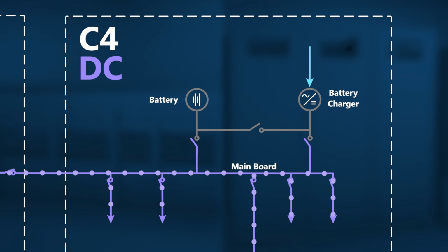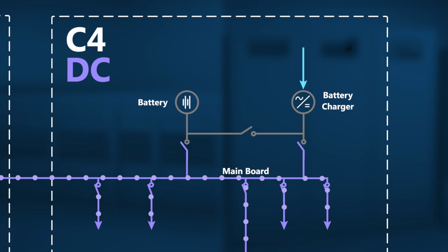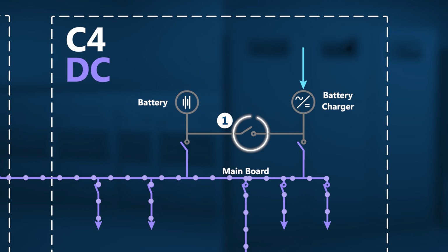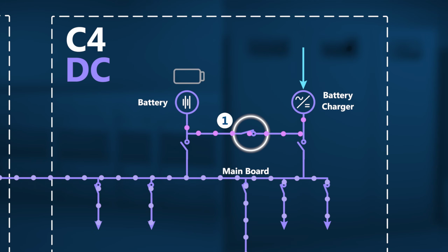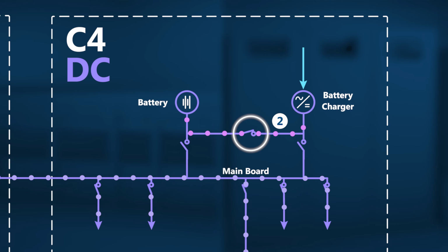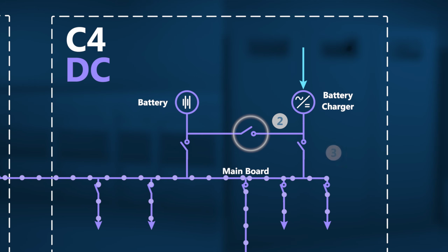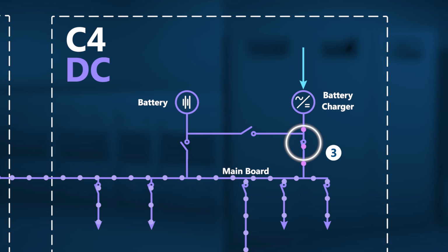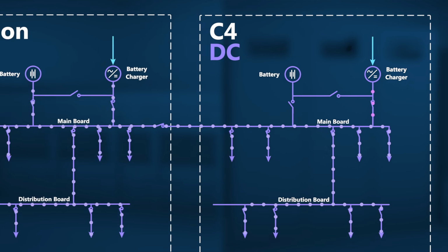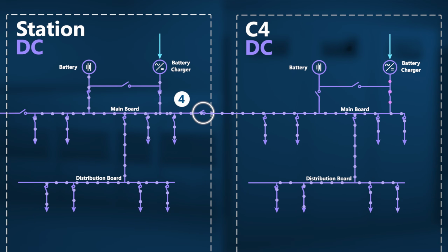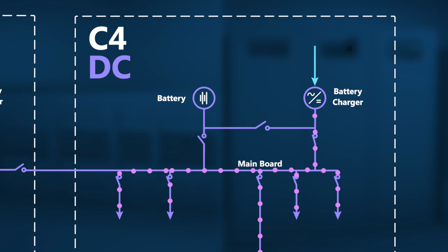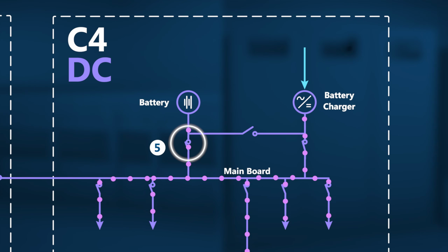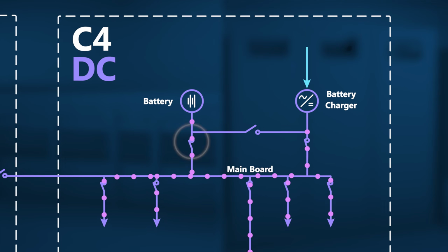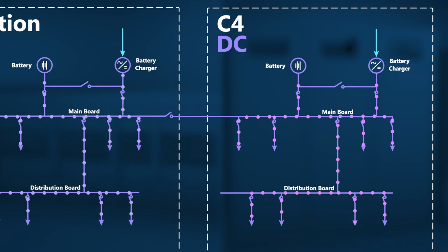The planned switching sequence had 5 key steps. Firstly, the battery charger would be connected directly to the battery to restore it to a full state of charge. Once the battery was charged, the battery charger would be disconnected. It would then be connected to the C4 system. Then the interconnector from station would be opened, disconnecting station and C4. Finally, the C4 battery would be reconnected. These steps would restore the system to its typical configuration.